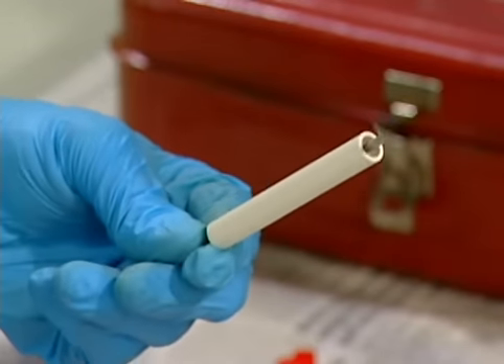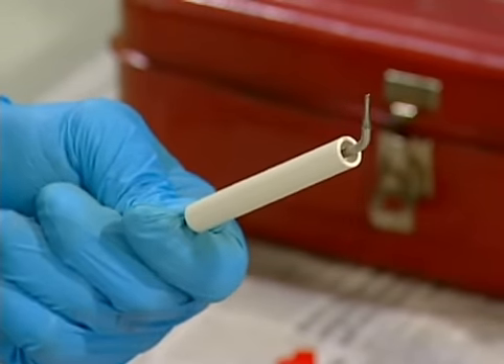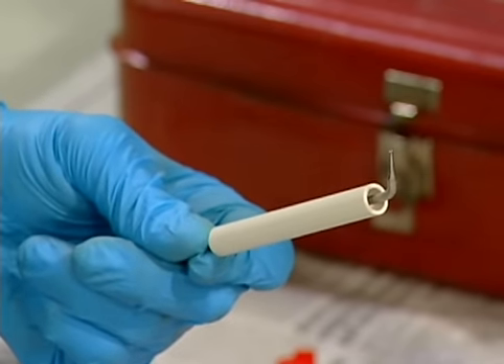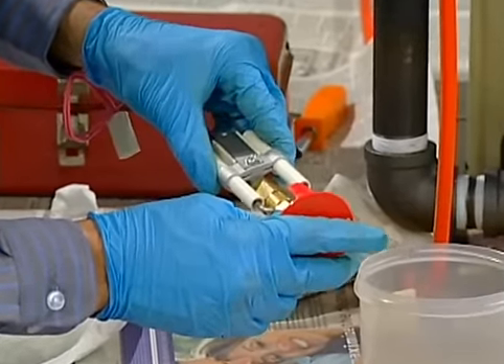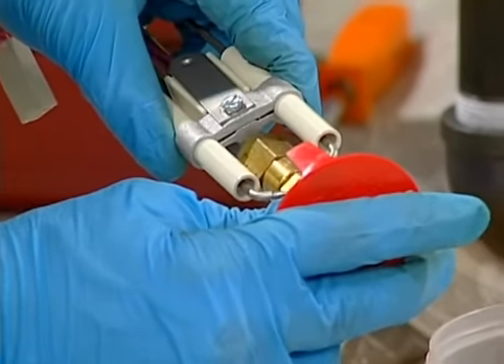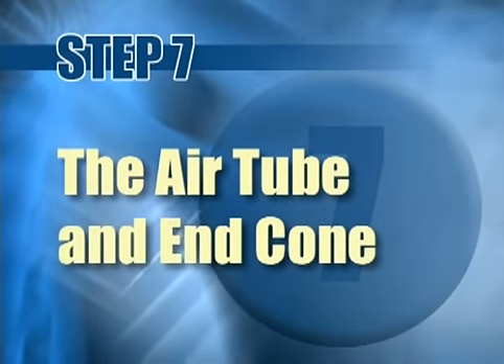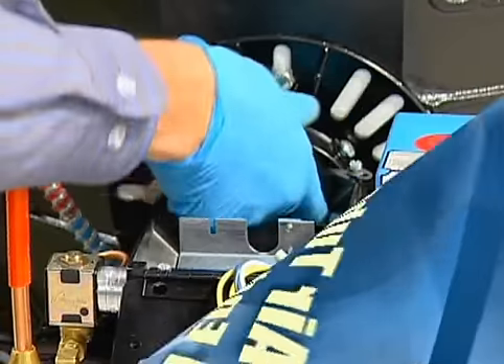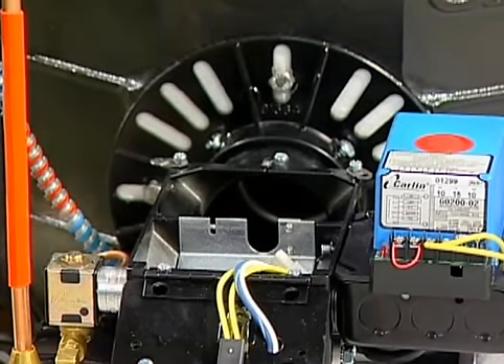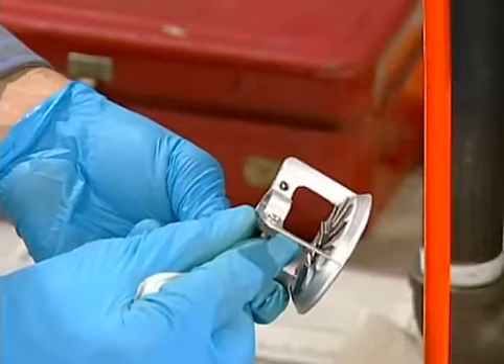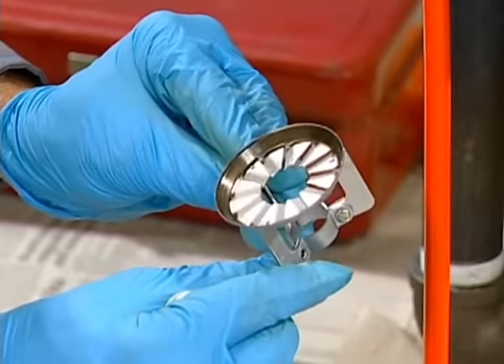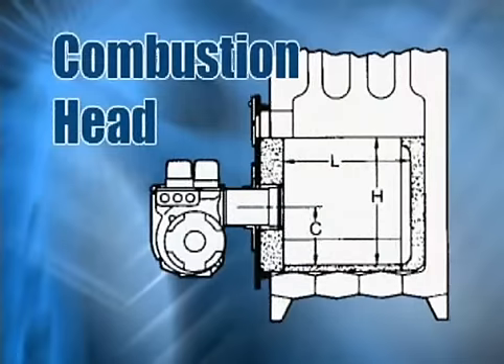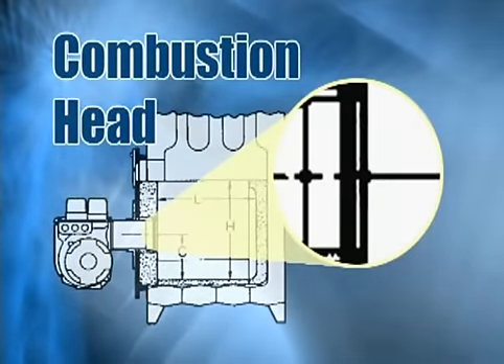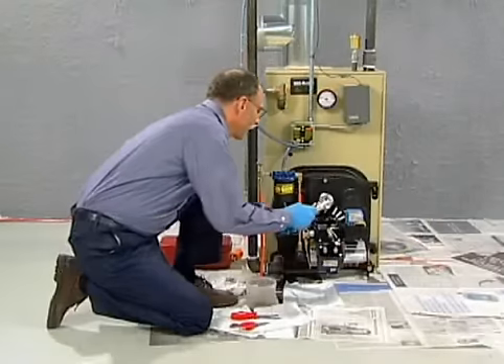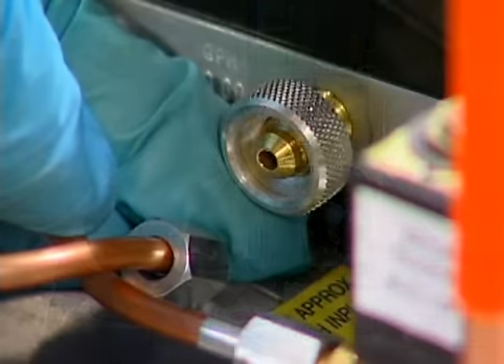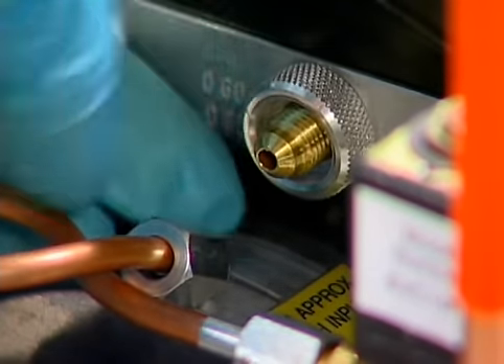Clean and inspect the electrodes and the porcelains. Check the ends of the electrodes for deterioration and the porcelains for chips or cracks. Adjust the electrodes to manufacturer's specs using the appropriate gauge. Clean and inspect the air tube along with the end cone slots and holes. Check the end cone or flame ring to be sure it isn't warped, burned out, or covered with carbon. Be sure the combustion head doesn't extend into the chamber. It should be recessed. Reinsert the nozzle assembly into the air tube and secure it in place, making sure it's in the same position that you marked earlier.